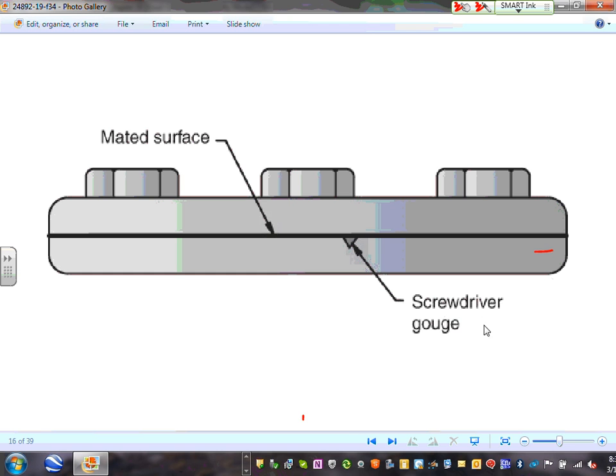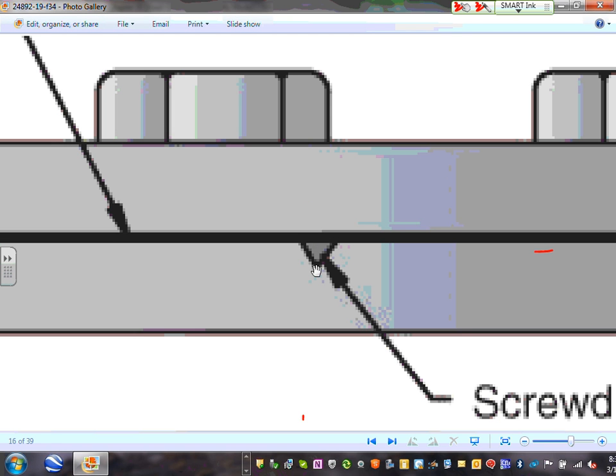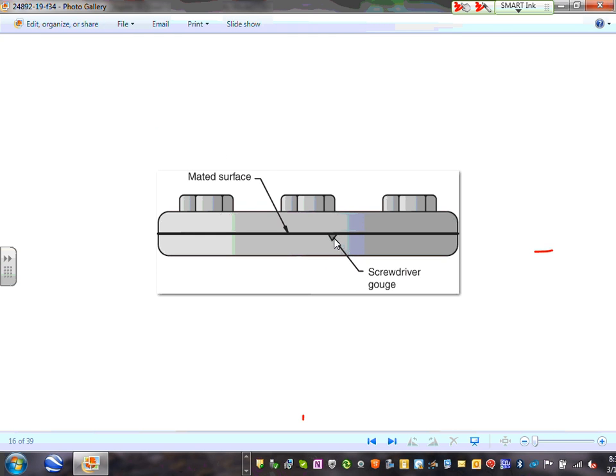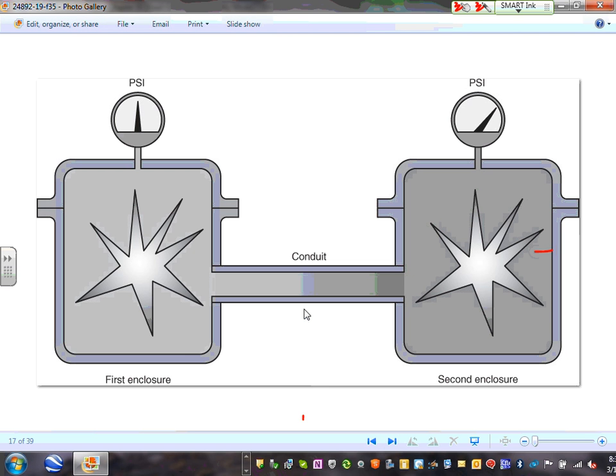Mated surface, screwdriver gouges here. If you make a hole here, can you see that? Little hole, that will screw up the whole system. So you make sure that you don't damage, Adam, when you install these, you do not damage the surfaces when you install them. This is called pressure piling, guys. If you have an explosion in this one here, and it seeps into this one, the second enclosure will have double, triple the pressure that the first enclosure had if you channel them.